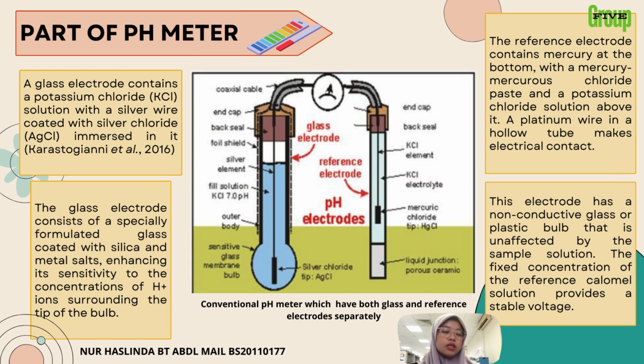The glass electrode is designed with a potassium chloride (KCl) solution and a silver wire that's coated with silver chloride (AgCl) immersed in it. This electrode uses a specially formulated glass coated with silica and metal salt, making it very sensitive to the H+ ion concentrations around the tip of the bulb. On the other hand, the reference electrode has a different setup. At the bottom of the reference electrode tube, there is mercury covered with a paste of mercury and mercurous chloride. Above this paste, a potassium chloride solution is placed, and a platinum wire sealed in a hollow tube helps make the electrical contact.